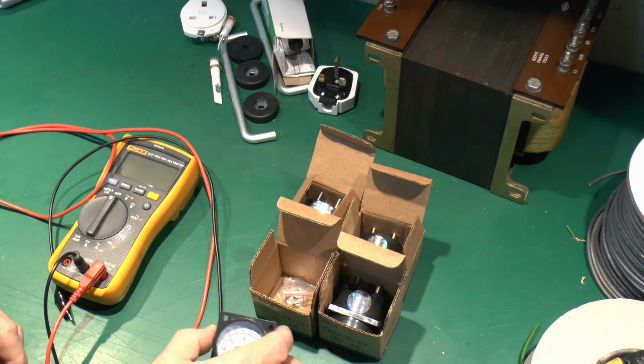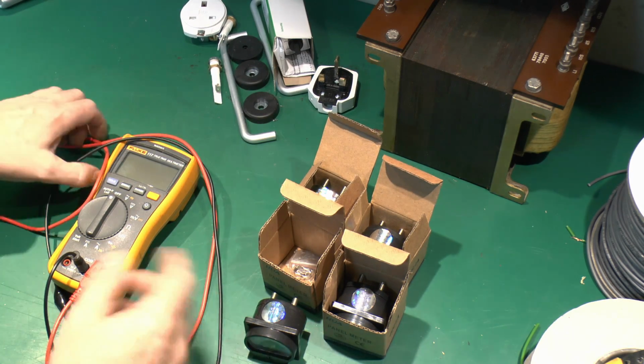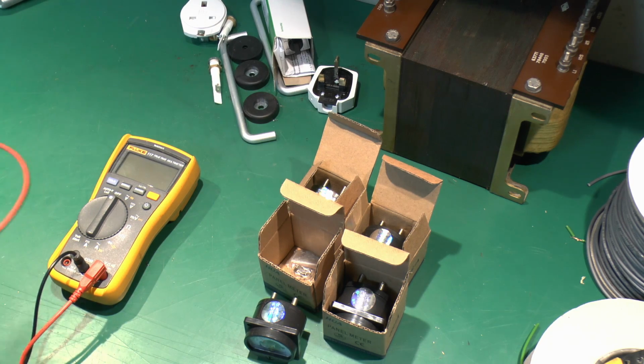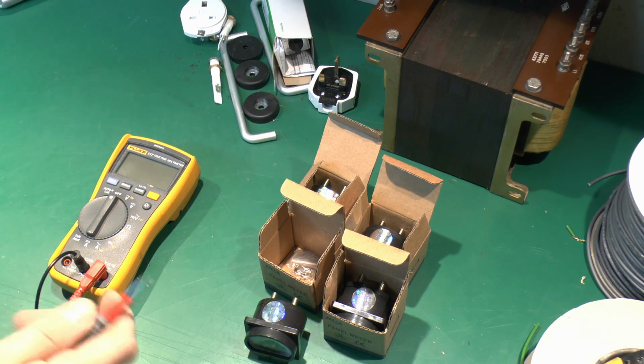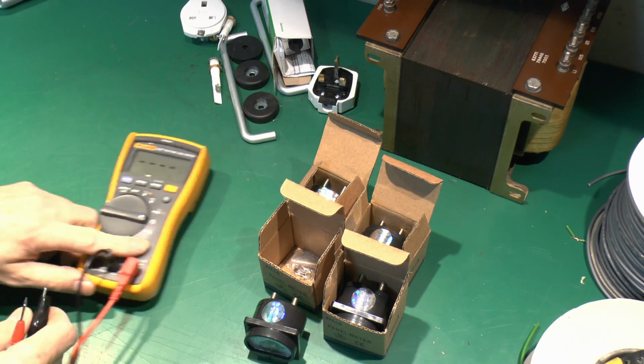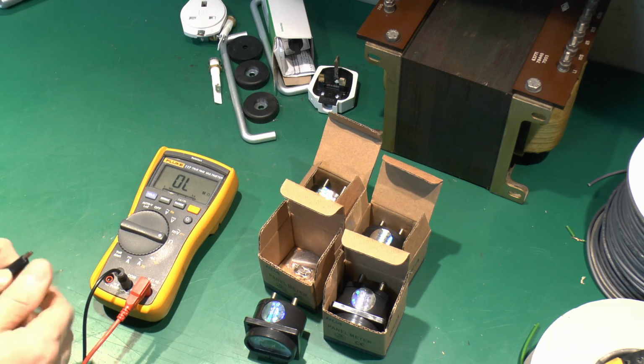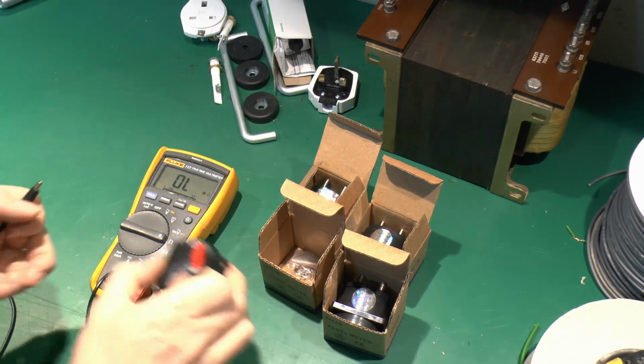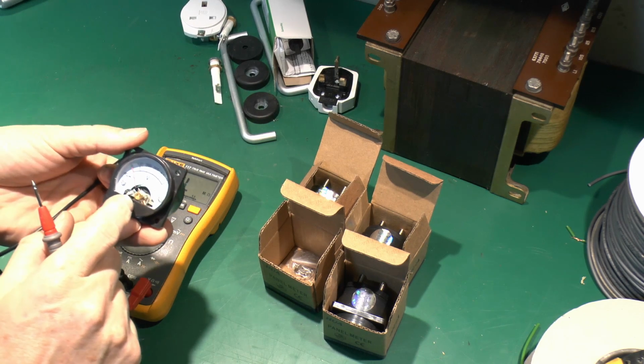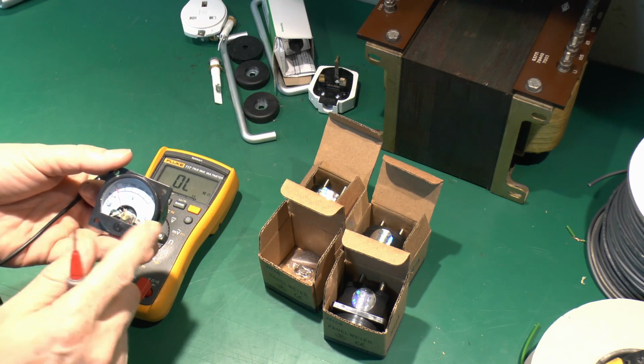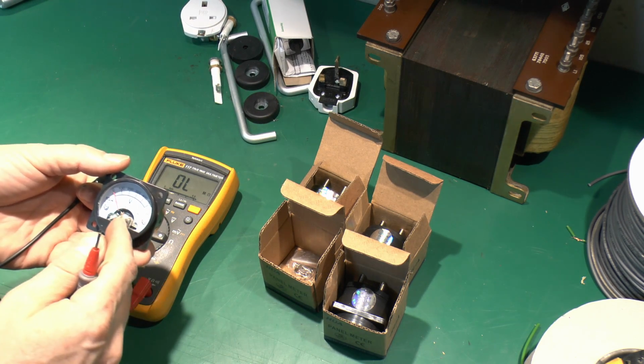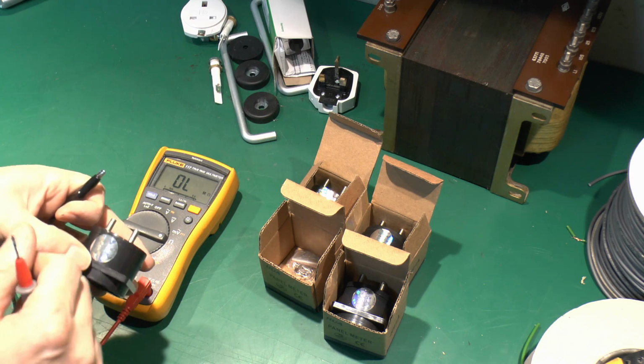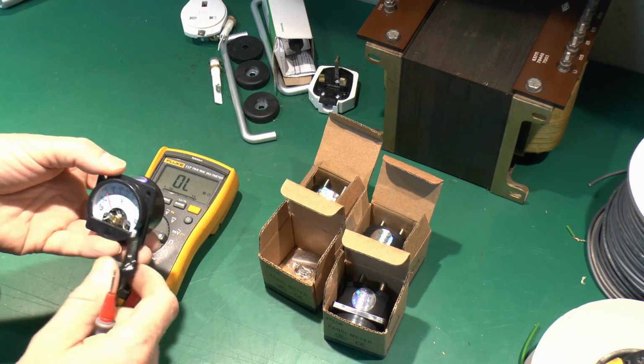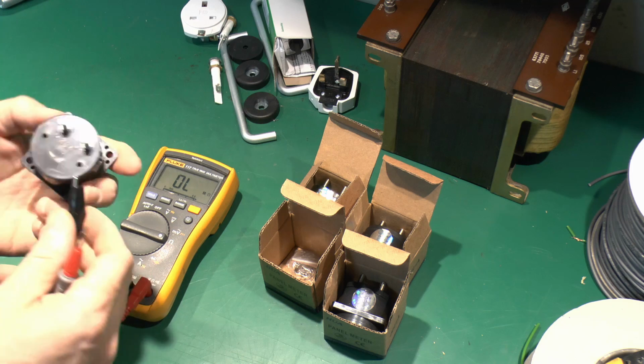Now I'm just going to check these to make sure they are in fact what they claim to be on the front, because if they weren't, we could end up connecting it and something could blow up. So I'm going to turn the meter to resistance and check the resistance of these things. These are voltmeters designed to connect directly across the supply up to 500 volts, so we'd expect the resistance between these to be extremely high, hopefully in the order of mega ohms. Let's check these.